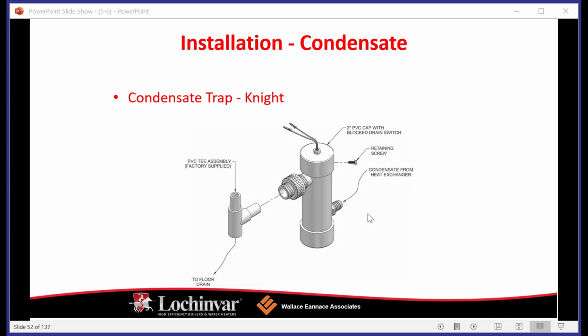Okay, so condensate, we're going to double back on this. We talked about condensing, modulating, and turndown. We also talked about flue gases containing water. One of the ways that we get this efficiency is from a condensing boiler. As the energy travels through the heat exchanger in the form of flame, on an older atmospheric cast iron boiler, it would travel through the heat exchanger and expel the flue gases into the flue, and it would change state from a flame to a vapor in the flue.